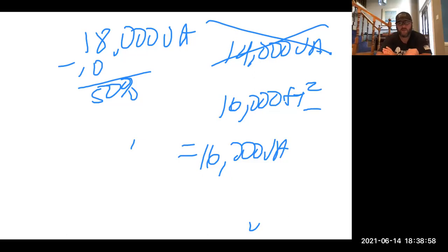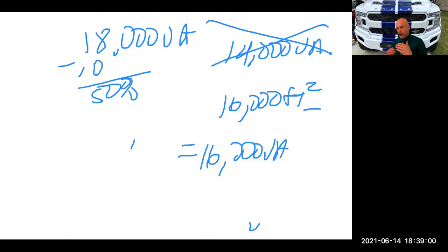So just remember, it's either the square footage at full face value times 1 VA or your calculated value, whichever is the larger of the two calculated methods, for banks or office buildings, either one, when it comes to receptacle loads.